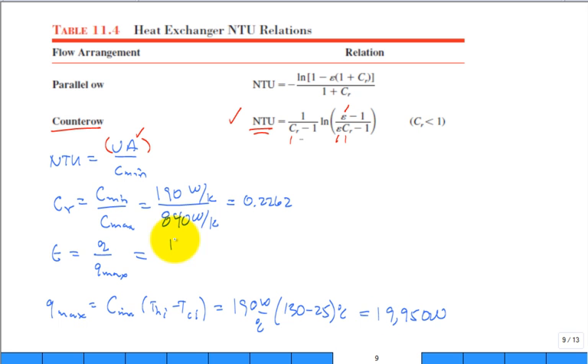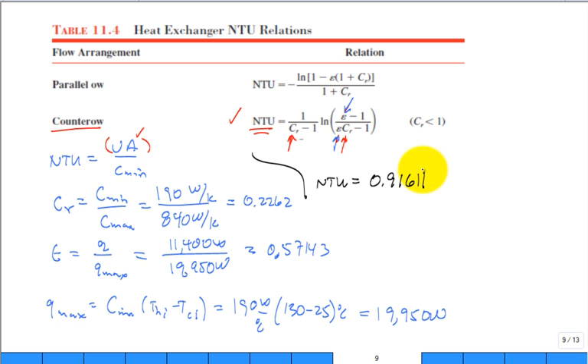So we had 11,400 watts, the actual, divided by 19,950 watts. Doesn't it seem like you're going a completely different route? We're going to get the same answer. But we're using the effectiveness NTU method. This comes in at 0.57143. So 57.143%. So put that in for the effectiveness there. Put in for the C sub R there. And you calculate the number of transfer units. It comes in at 0.91611.